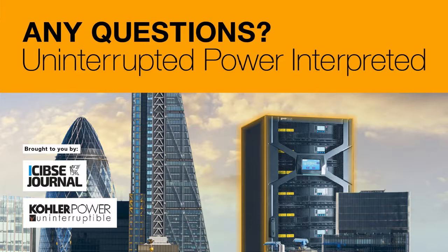which is a little bit different to the standby generators. Modern generators, providing we have modern generators with electronic governors, it does depend on the type and make of generator compared with the type and make of UPS. But that is really a question to the actual individual manufacturer. But typically, generator interfacing with UPSs is much better now than it was 10, 20 years ago, due to the advances on the rectifiers of the UPSs. They're much kinder to generators nowadays. Okay, thank you very much.